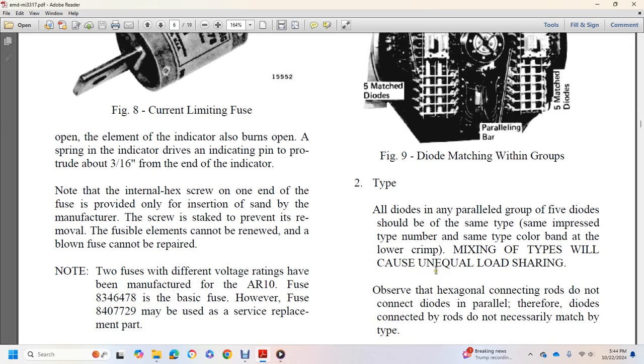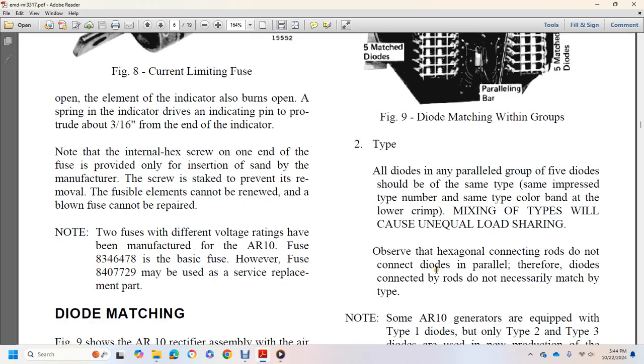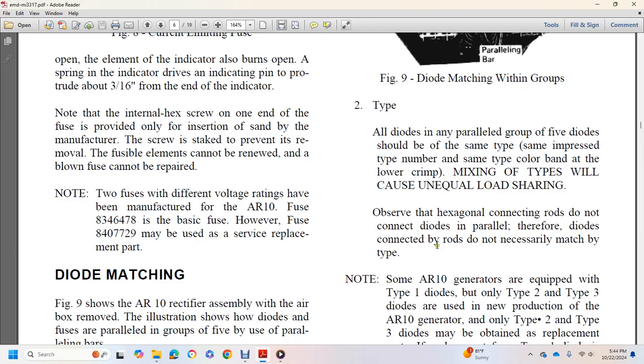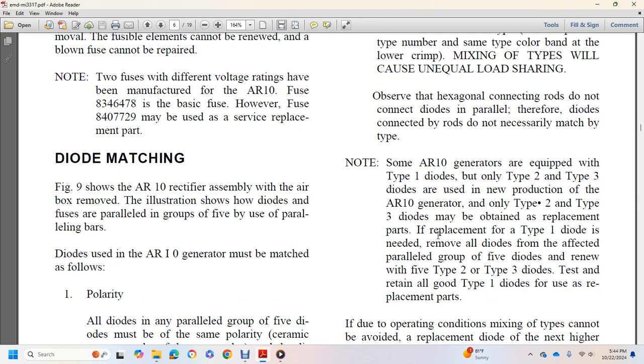Type: all the diodes of the parallel group of five diodes should be the same type, with the same color band on the lower crimp. Mixing types could cause unequal load sharing, so the diodes connected in parallel must match in type. Note: some of the AR10s are equipped with type 1 diodes, but only type 2 and 3 diodes are used in the new production of AR10 generators. Only type 2 and 3 diodes may be obtained as replacement parts.